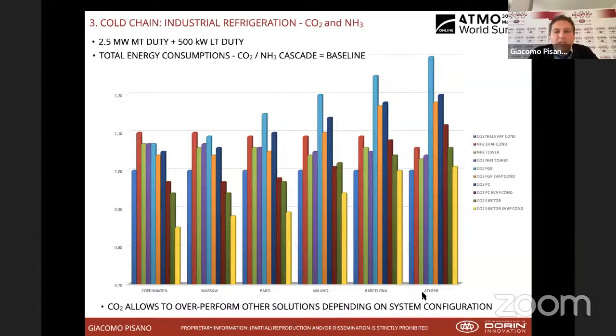If you do the same comparison in Athens and take into consideration, again, the benchmark, CO2 cascade with ammonia with evaporative condenser against CO2 flash gas bypass, you can see that CO2 flash gas bypass in a year of operation is about 30% less efficient than the baseline. So clearly you will need to implement evaporative cooling with CO2, parallel compression and ejector. But using ejectors, evaporative condenser and parallel compression enables full CO2 transcritical technology to approach the baseline, which has been set as ammonia and CO2 cascade.